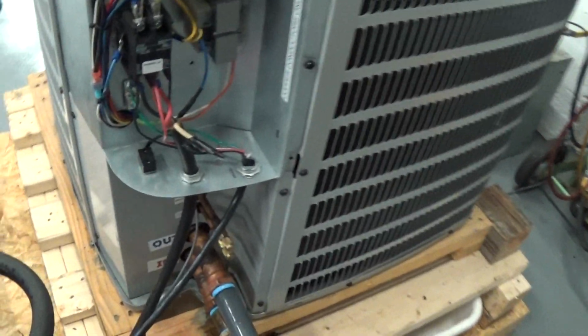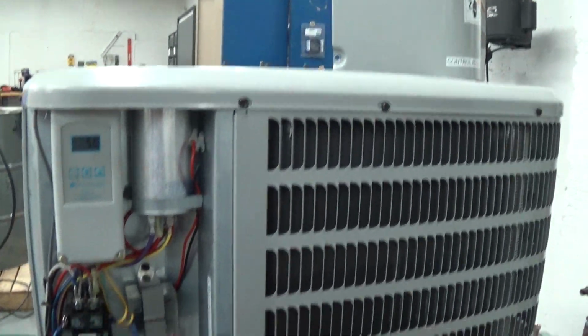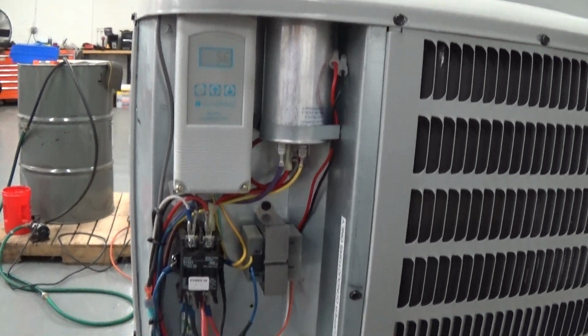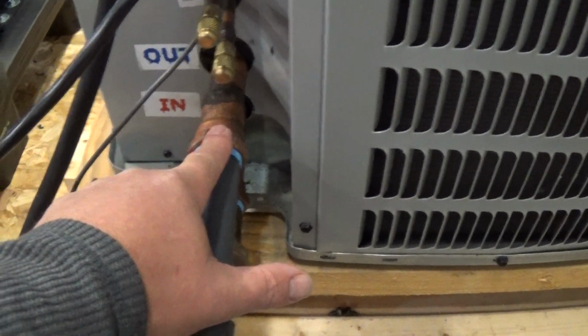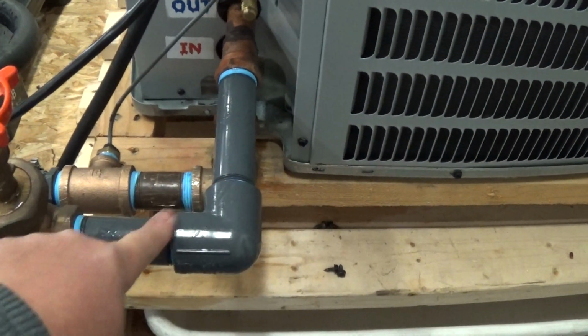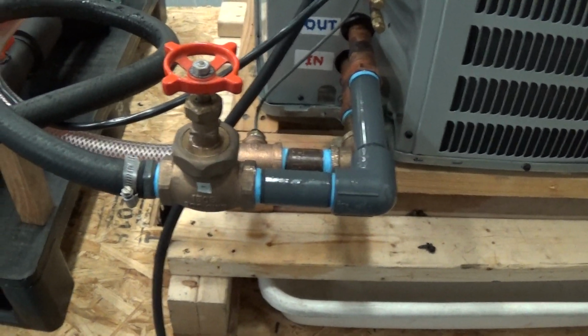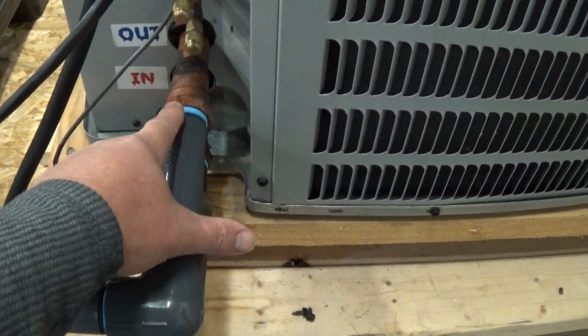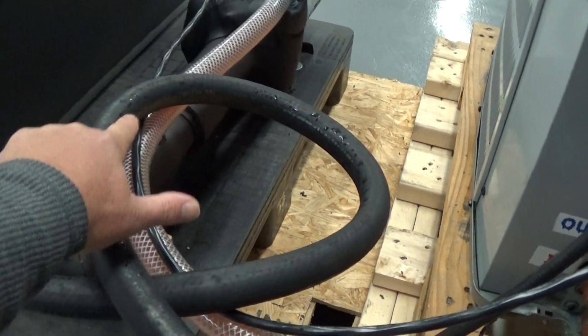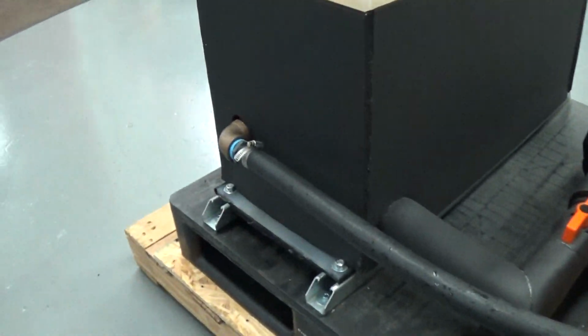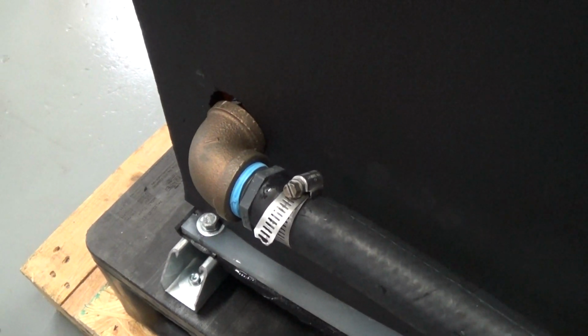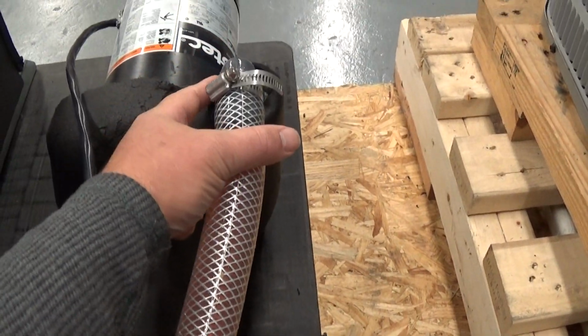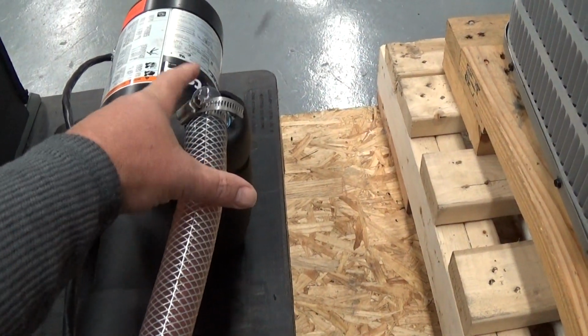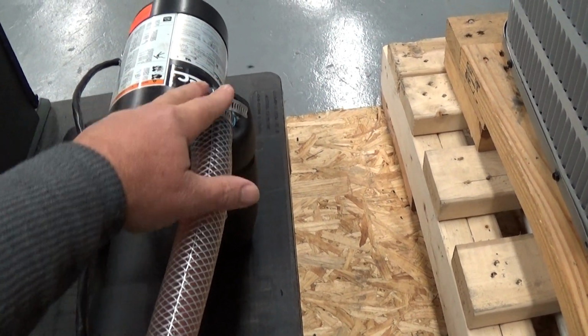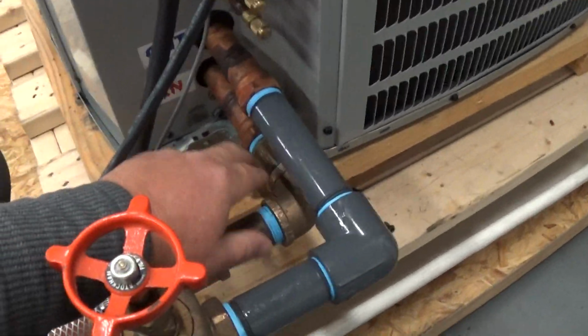So what the customer's going to do is probably mount the condenser assembly outside, and this is the controller and electrical assembly. We have the covers for that. This is the output, 1 inch NPT. This is going to be the supply line that goes out to your tank or tanks. In our test environment, the chiller ships with the output line here, and we just have it going back to the tank. That here is going to be your return back to the tank, okay? The pump draws from the bottom of the tank, and that's heavily insulated. And then this is the discharge, which is 1 inch, okay? This is going to ship just with an opening here. You're going to pipe it 1 inch from the discharge back into the chiller.